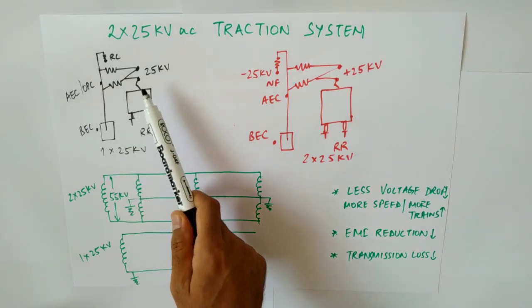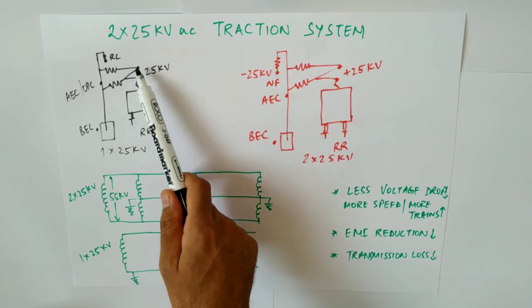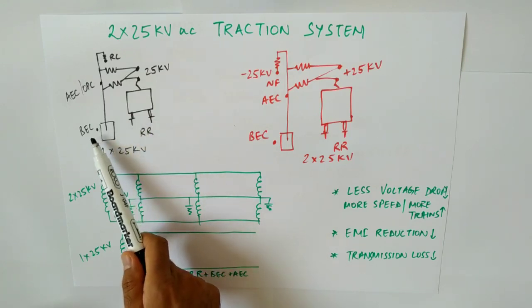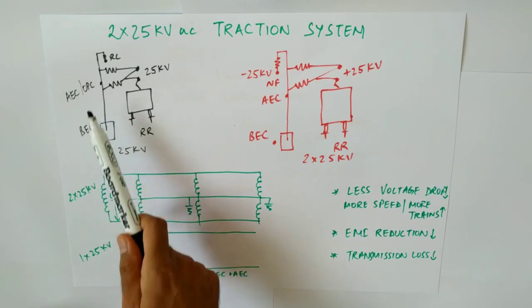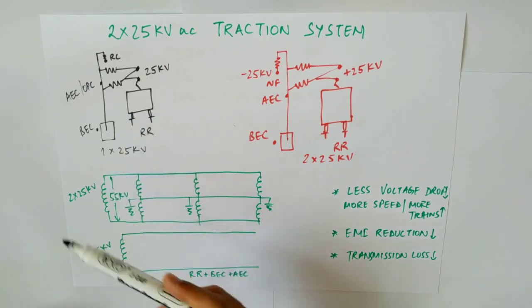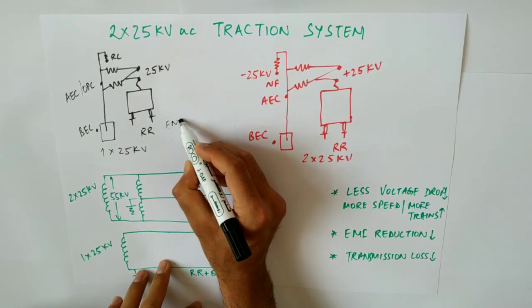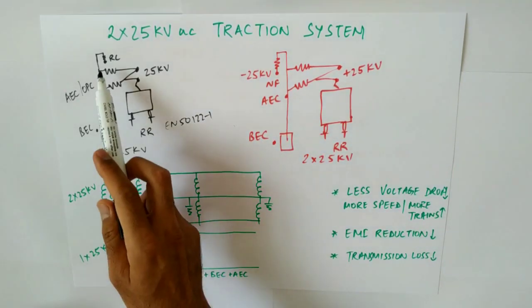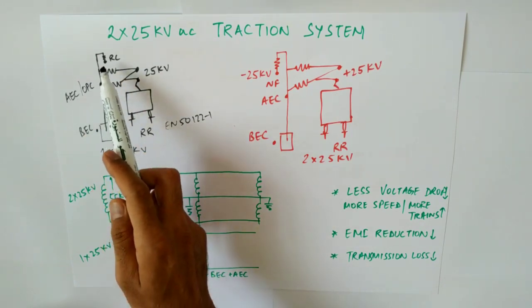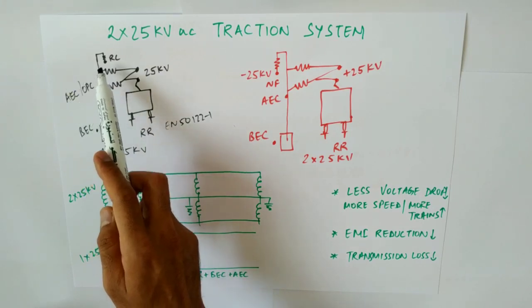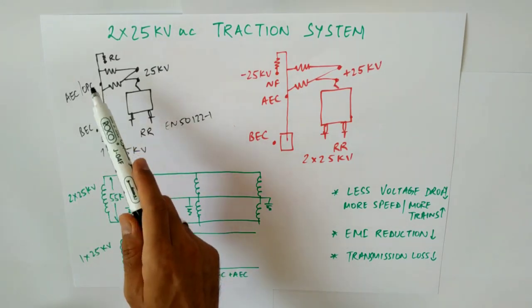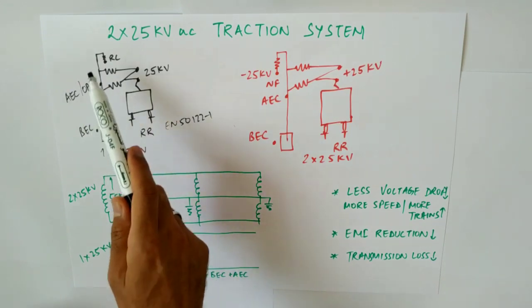In the 1×25 kV system, we have the OCS system — catenary and contact wire — carrying 25 kV supply, and then the running rails, buried earth conductor, and OPC, which are all connected together at regular intervals to reduce rail potential and maintain it as per EN 50122-1. The return conductors are generally around ground potential — they can be up to 60 volts but typically we say they are at ground potential.